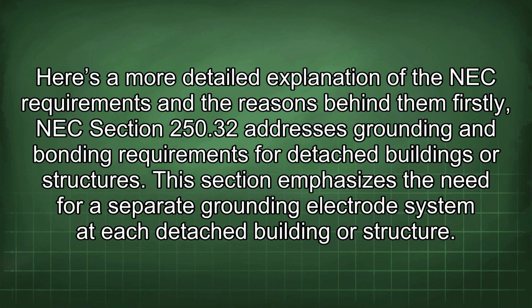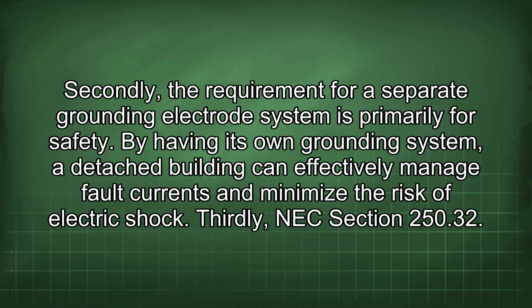Firstly, NEC Section 250.32 addresses grounding and bonding requirements for detached buildings or structures. This section emphasizes the need for a separate grounding electrode system at each detached building or structure. Secondly, the requirement for a separate grounding electrode system is primarily for safety. By having its own grounding system, a detached building can effectively manage fault currents and minimize the risk of electric shock.